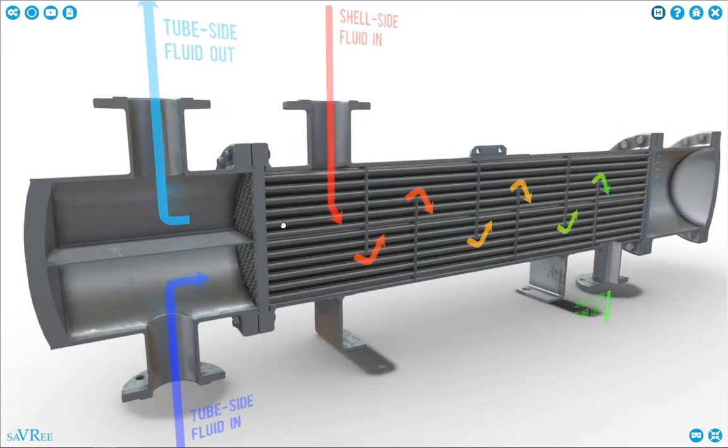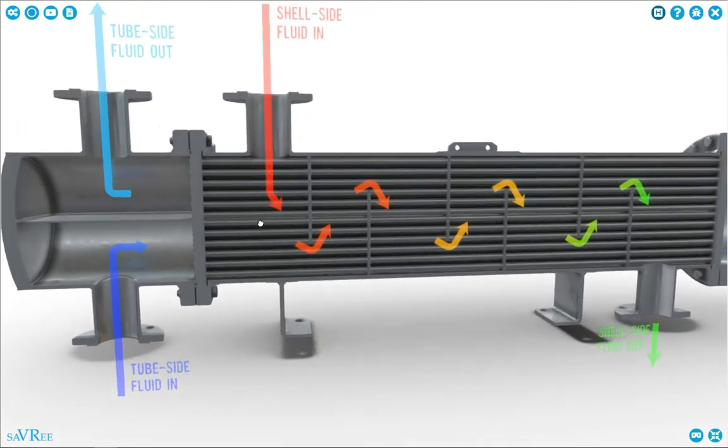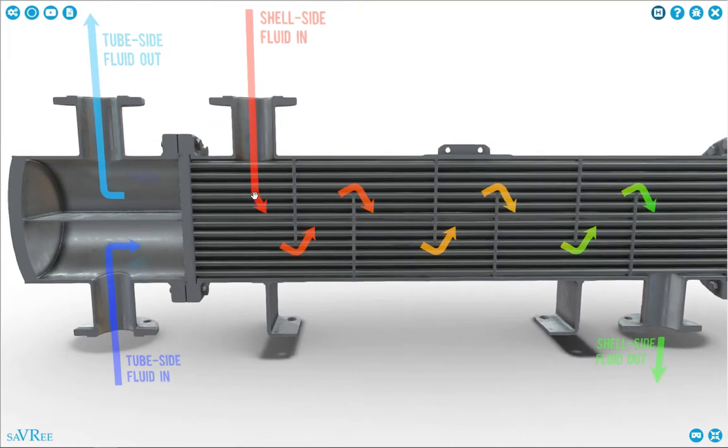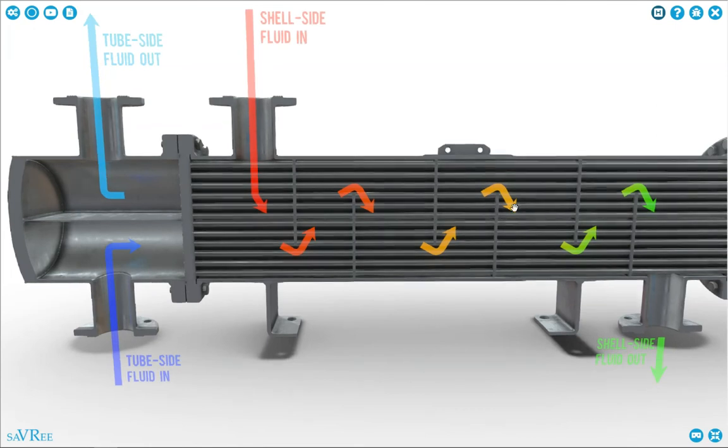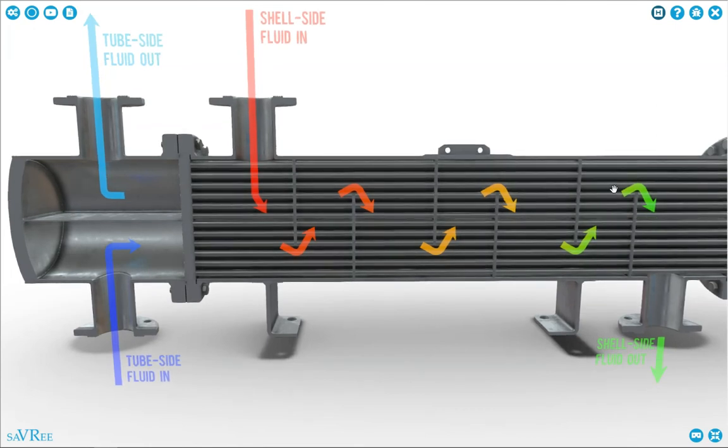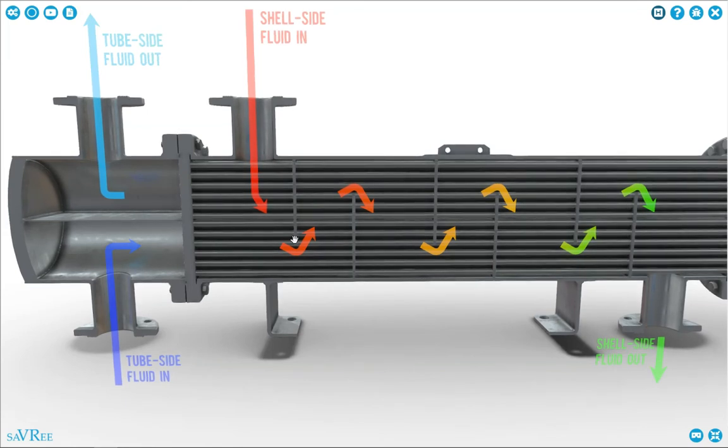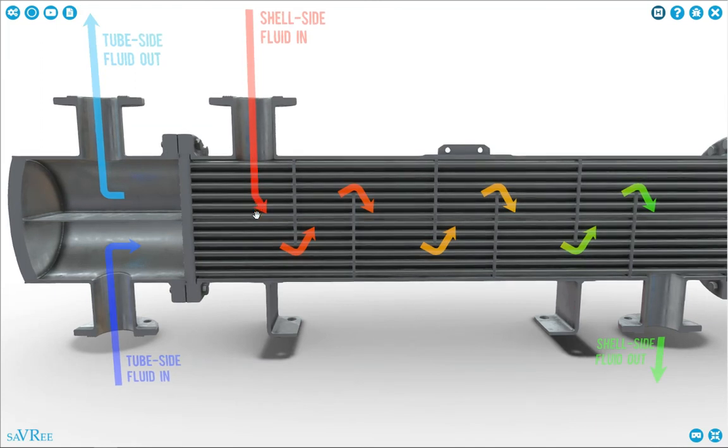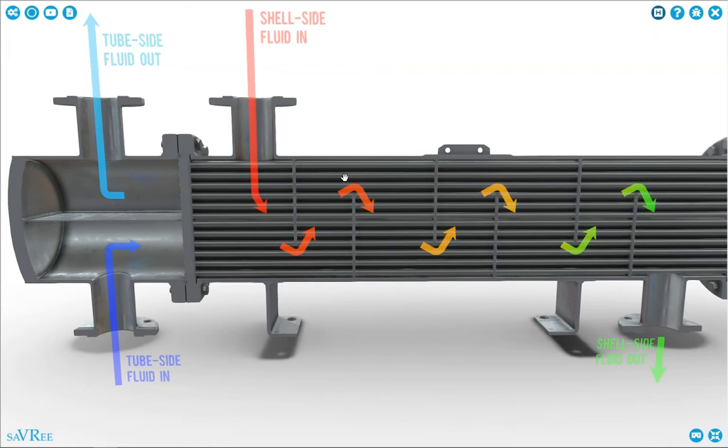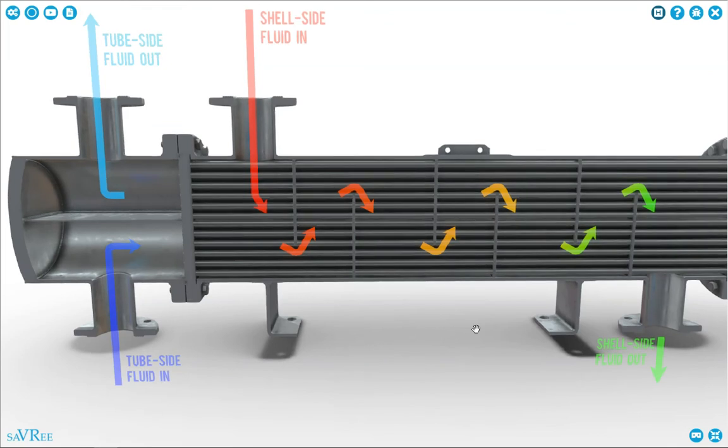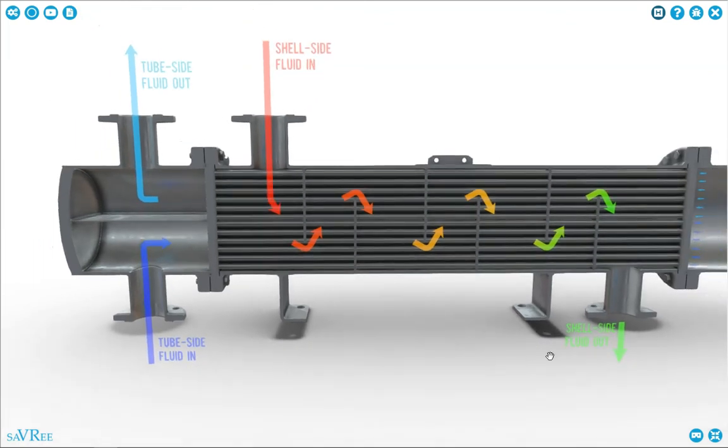We also have the other fluid that comes in. So we have the shell side, which has an inlet over here. And it exchanges its heat with the fluid that's in the tubes, and then eventually leaves over here. In order to maximize the heat transfer, we have these baffles that are inside of the pathway, which mean that our shell, or the pathway through that shell, is a much longer pathway, and it moves over top of tubes several times before exiting. And that means that we can have a little bit better heat transfer rate through that system.